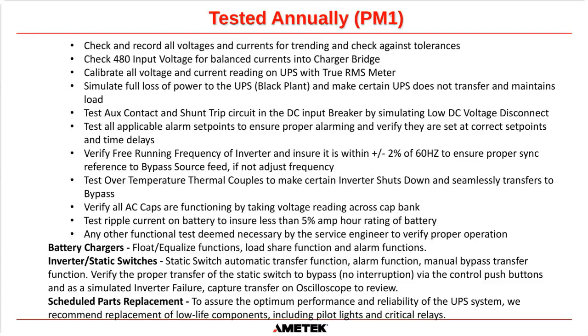We verify the free running frequency of the inverter to ensure it is within plus or minus 2% of 60 Hertz in North America. And that ensures proper sync reference to the bypass source feed. So basically, to do that, we have to remove the bypass supply into the UPS itself. We would put the system in the RMBS to the bypass position, and then we would run the inverter without any bypass to the UPS, and it would run at its own internal frequency. And we make sure that that is set correctly.